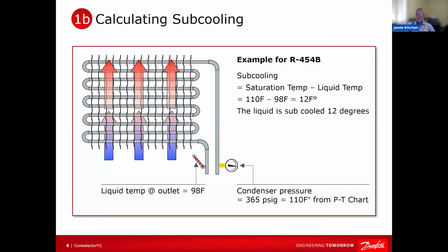Now, remember, this is important. From an efficiency standpoint, you are emptying the bucket in your condenser, and that is the same bucket you're going to fill in your evaporator. So the amount of heat that you can absorb in your evaporator, the amount of cooling you're going to do, is to fill that bucket up. So you have to go back to your condenser and empty it. So the subcooling is a way of further emptying that bucket so that when you go to your evaporator, you have more room to fill it up.